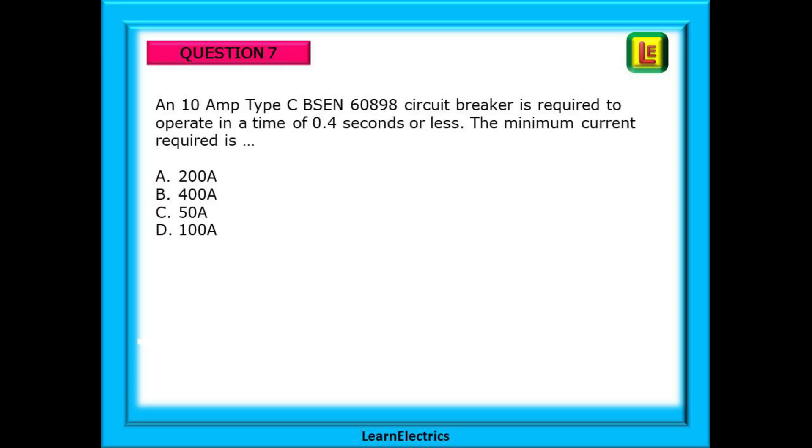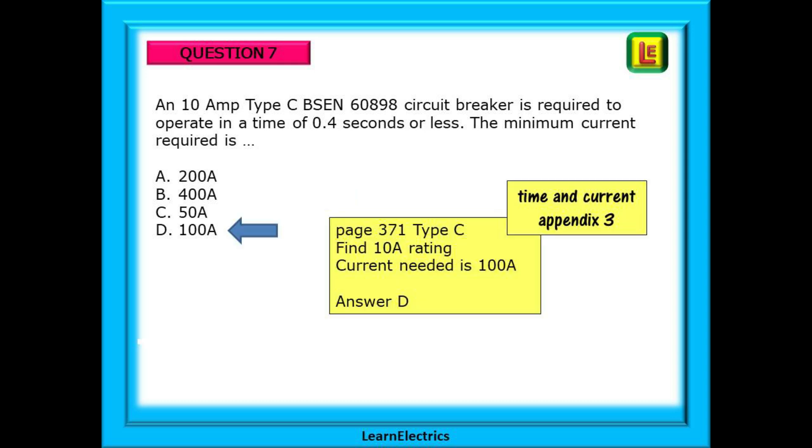And now question 7. The question is: A 10-amp type C BS EN 60898 circuit breaker is required to operate in a time of 0.4 seconds or less. The minimum current required is... Pause the video before continuing. This is a time and current question again, so the answer will be found in Appendix 3, on page 371. The fault current needed is 100 amps, so choose answer D.